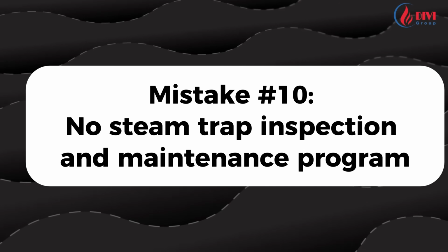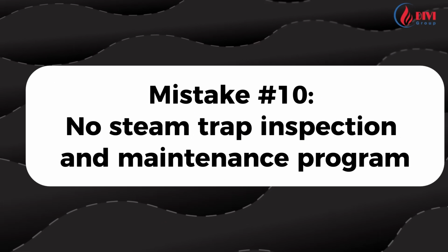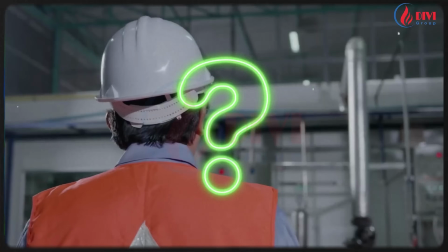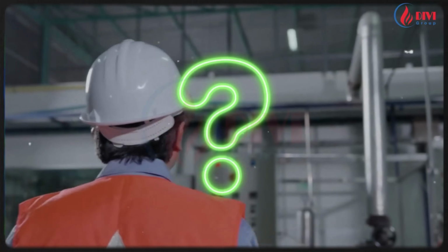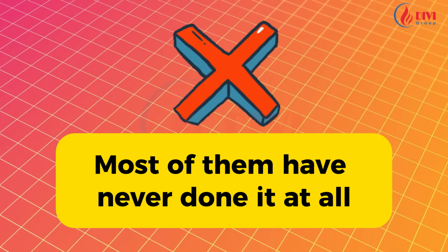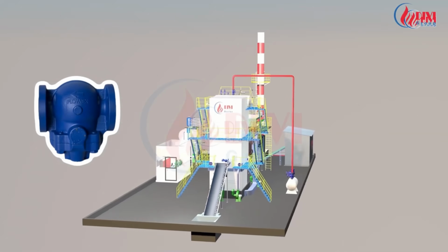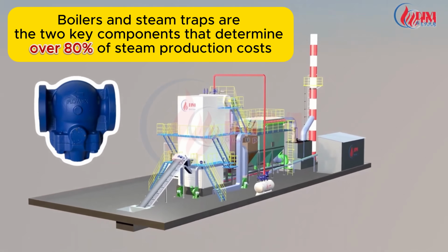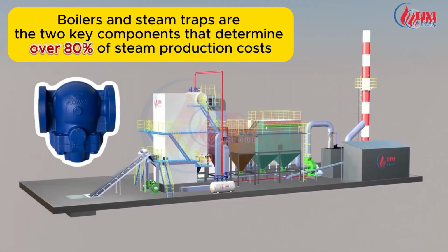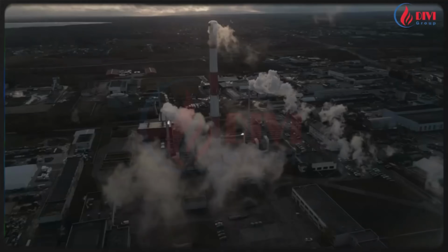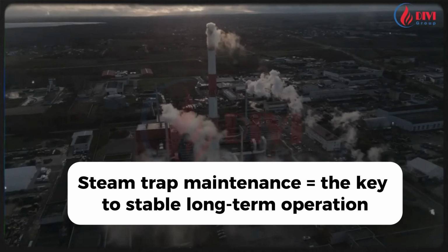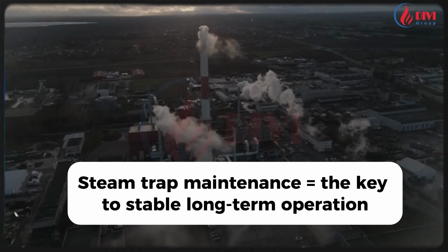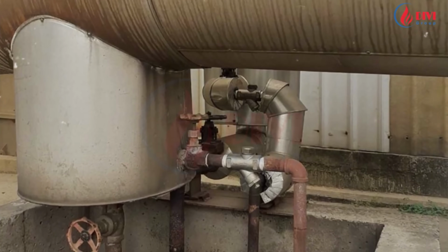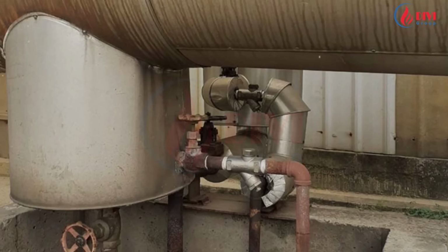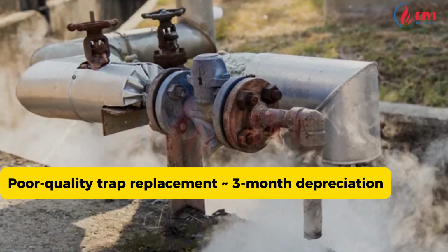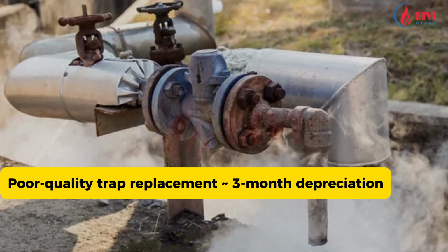Mistake number 10, having no inspection or maintenance program for steam traps. I have asked many factories, even very professional ones, and most have never inspected or maintained their steam traps. In steam production costs, the boiler and steam traps are the two most crucial factors driving overall operating expenses. Therefore, maintaining steam traps is essential for ensuring long-term system stability. Perform inspections regularly and replace damaged or low-quality traps immediately. Upgrading to high-quality traps typically pays for itself in under 3 months.